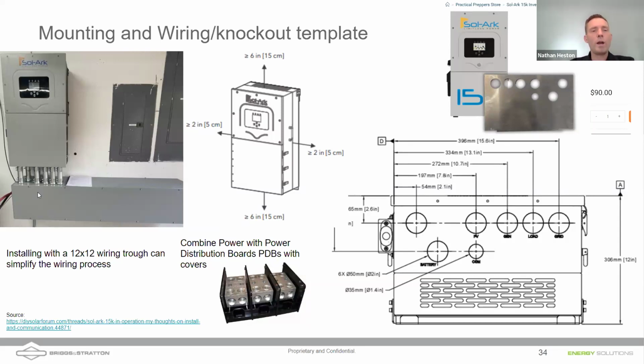And inside that wireway, you can mount your power distribution boards with those compression fittings for combos, especially when you're doing parallel units. The dimensions are here on the screen. You do need 6 inches above and below the inverter. So we're barely getting it here with this design. To the left and to the right, you do not need much space.